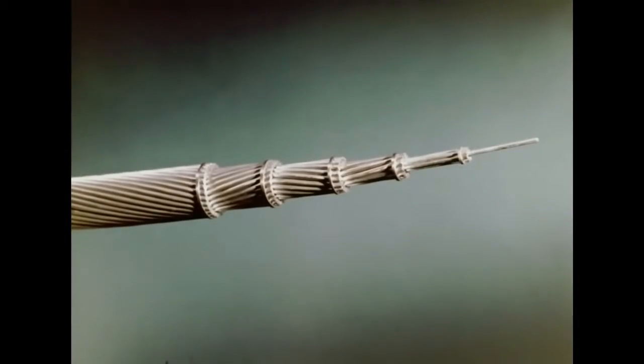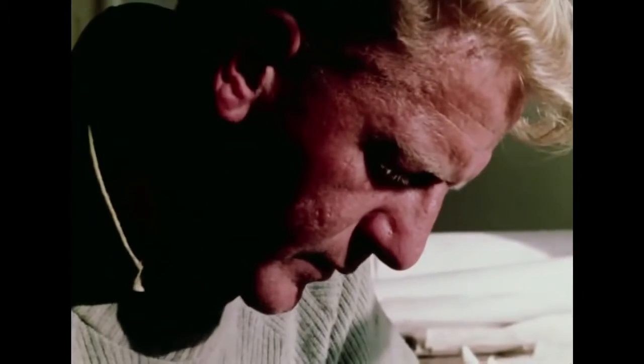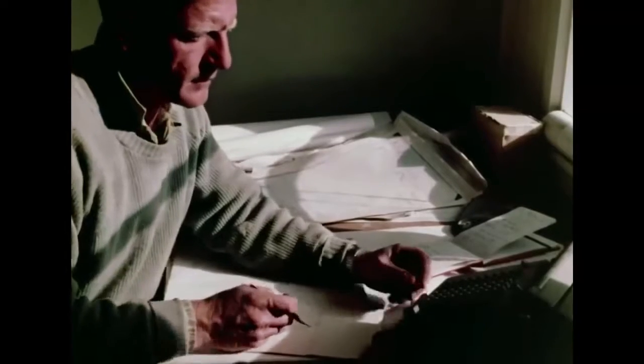The steel core within the conductor cable consists of 7 wires. It carries 76 aluminium conducting wires wound in 4 more layers. The correct sag of the conductors has to be fully calculated for spans between towers. Allowance must be made for the temperature at the time of sagging and also for future creep.